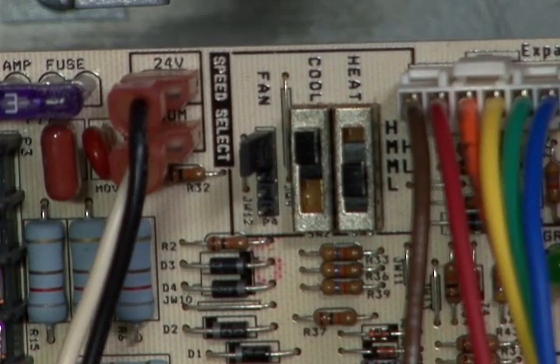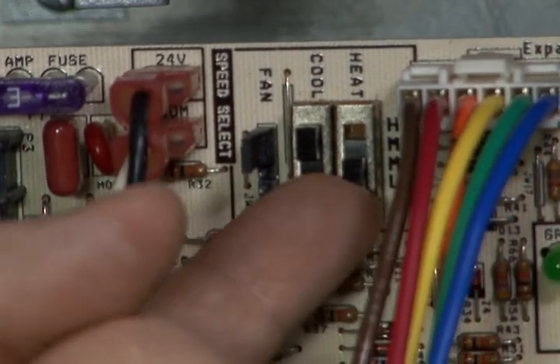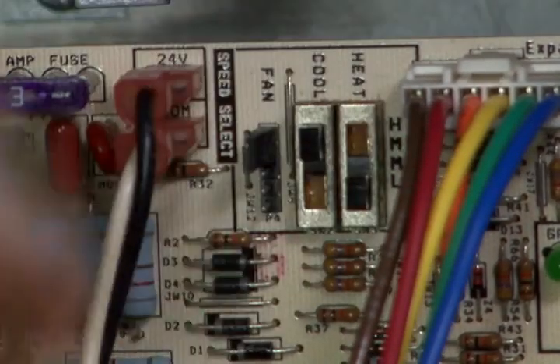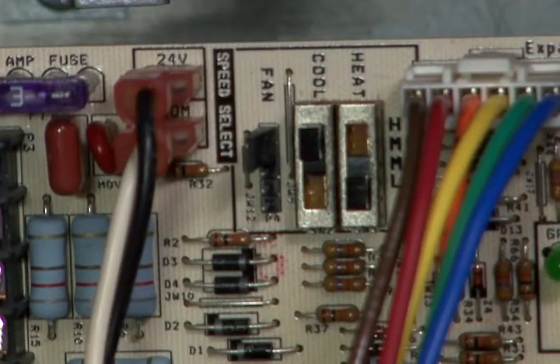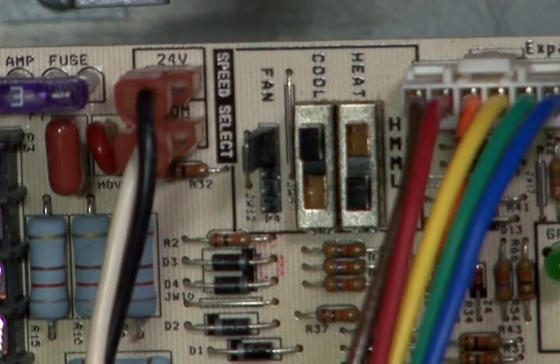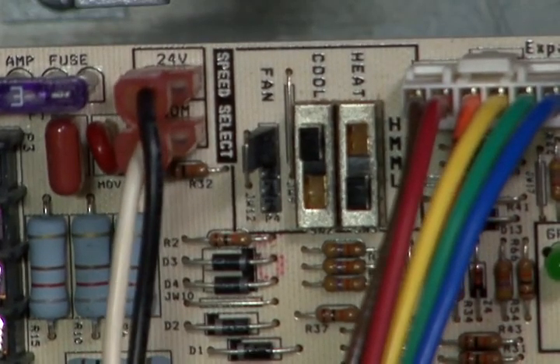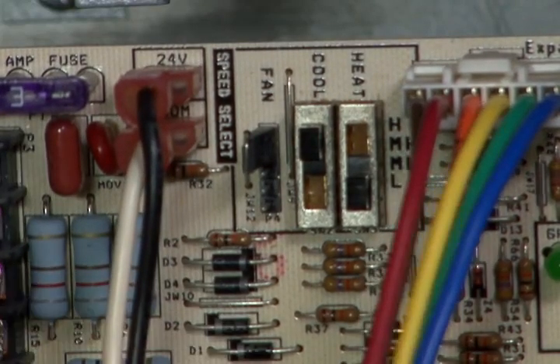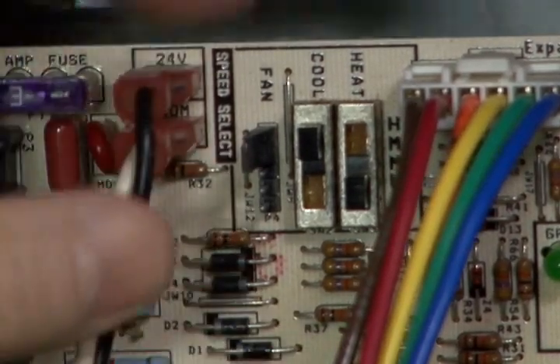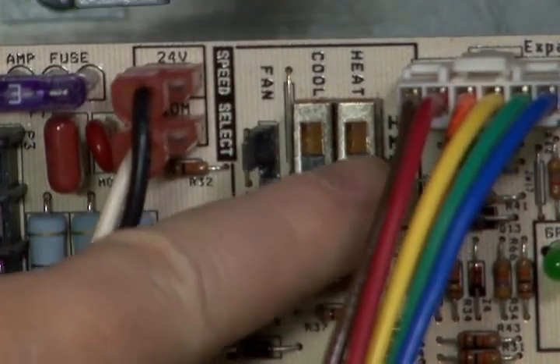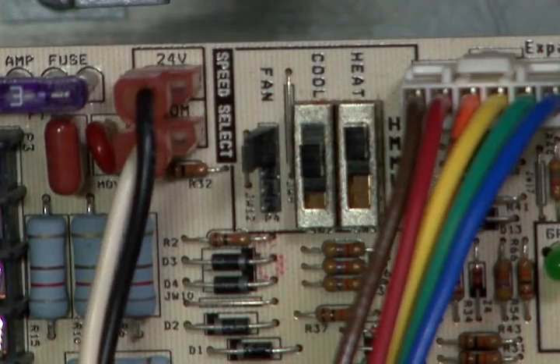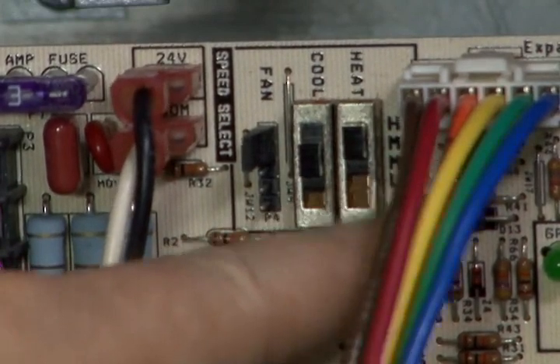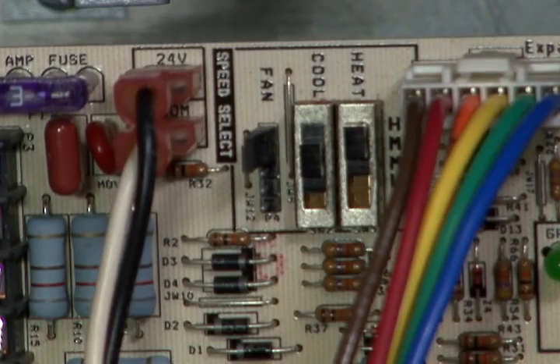And so when you need to set the blower speed, all you're going to do is move the position of the switches and line it up with the designated speed. You don't have to sit there and try to identify a wire and pull it off and then relocate it on a different tap or anything like that. All you're doing is setting the blower speed where you would like it by lining it up with the designated speed, if you will.